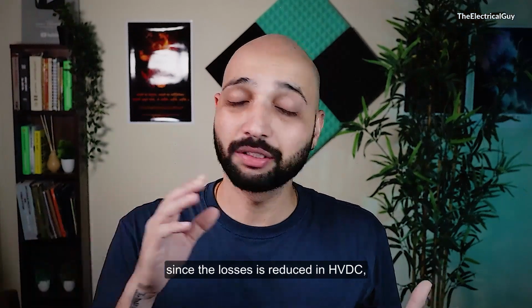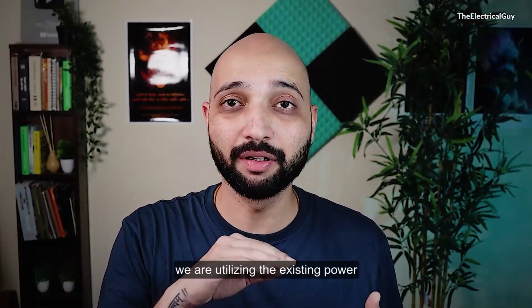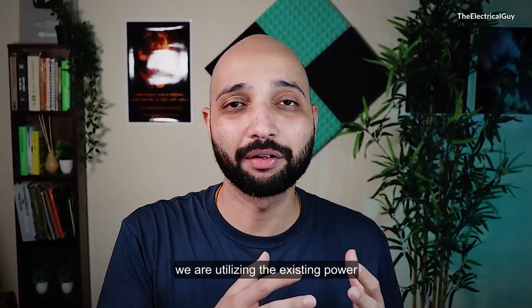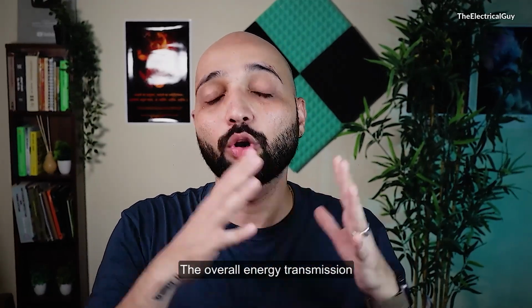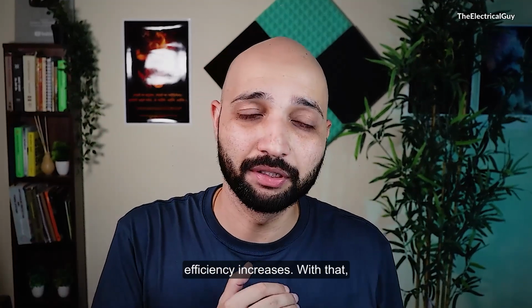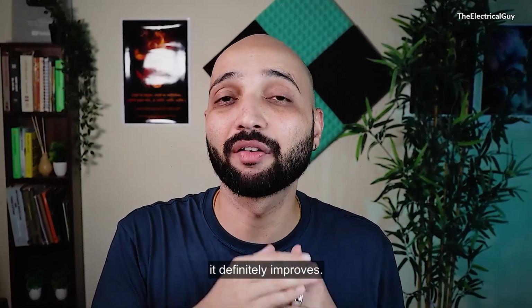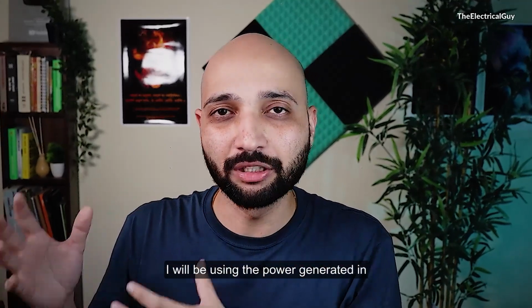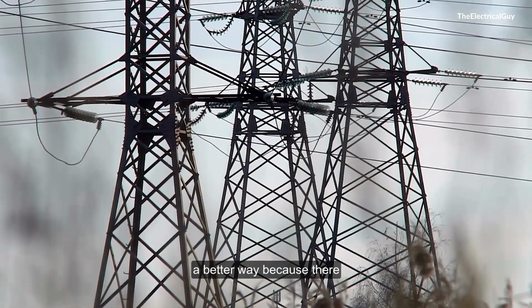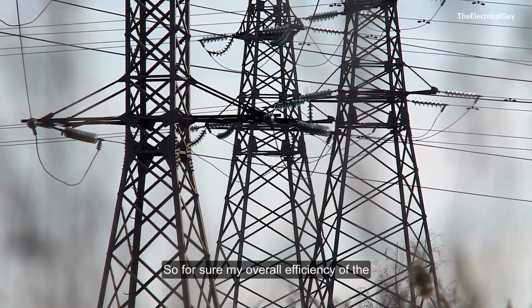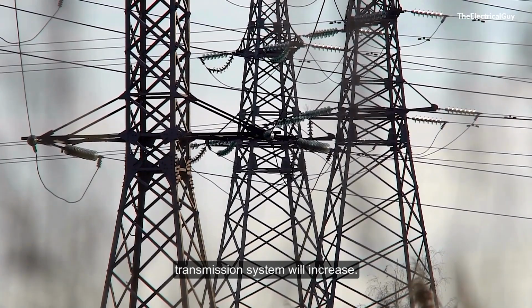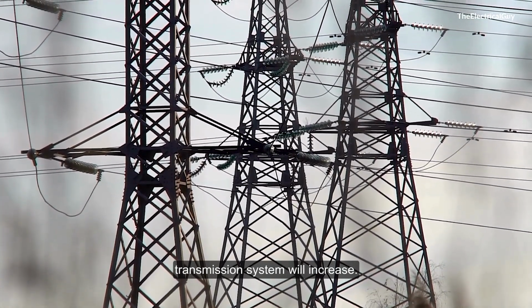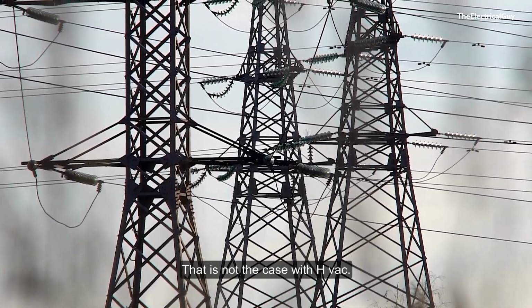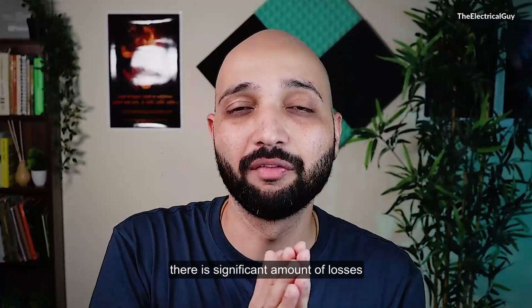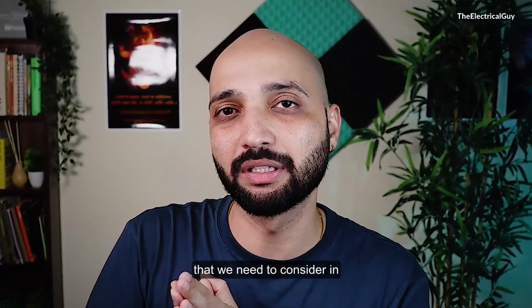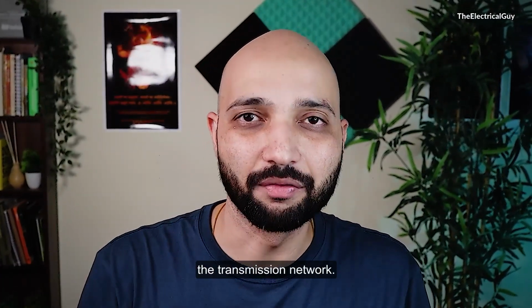Now, since the losses are reduced in HVDC, we are utilizing the existing power system in a better way. The overall energy transmission efficiency increases with that. I will be using the power generated in a better way because there are fewer losses, so for sure my overall efficiency of the transmission system will increase. That is not the case with HVAC, because in HVAC there is a significant amount of losses that we need to consider in the transmission network.